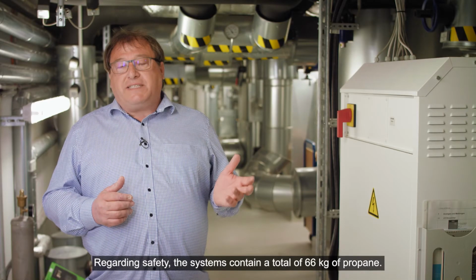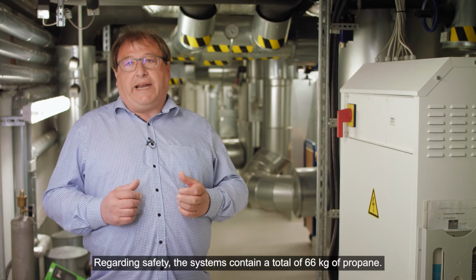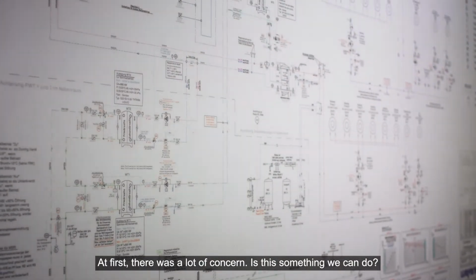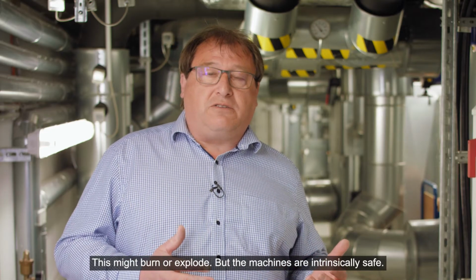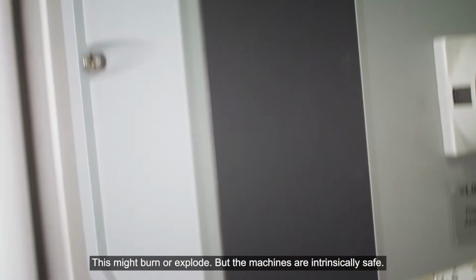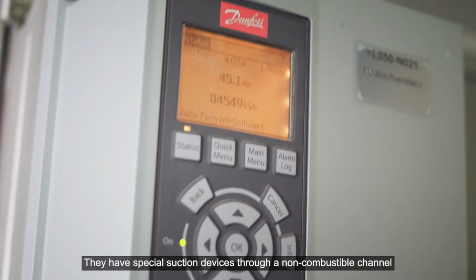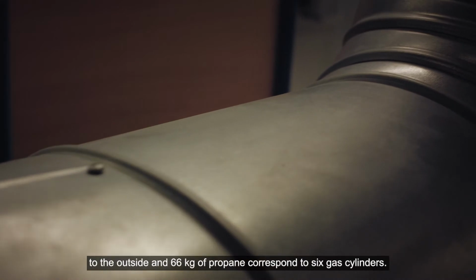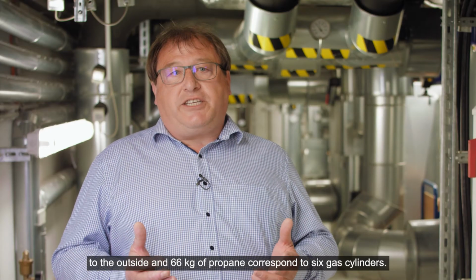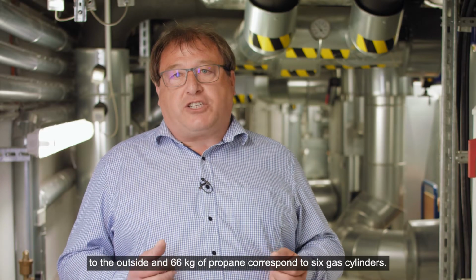Regarding safety, the systems contain a total of 66 kilograms of propane. At first there was a lot of concern. Is this something we can do? This might burn or explode, but the machines are intrinsically safe. They have special suction devices through a non-combustible channel to the outside, and 66 kilograms of propane correspond to 6 gas cylinders, so the danger is very low.